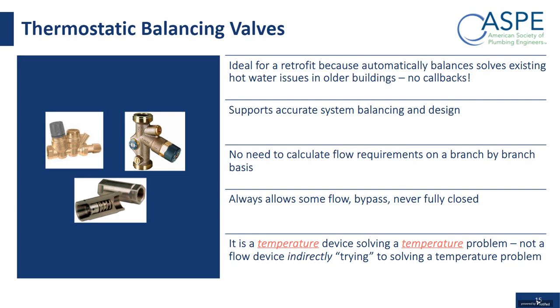I used to call that desperation installations, basically. A lot of this started out with hotels, dormitories, or multifamily units where the building wasn't getting hot water. They tried everything. They tried balancing several times and it wasn't working. Then they would increase the mixing valve output temperature or increase the size of the pump, and they still weren't getting it. The bottom line was that the system wasn't balanced and they just couldn't get it balanced properly. So out of desperation, I guess they went on Google or somewhere and searched balancing valves and came up with thermostatic balancing valves.